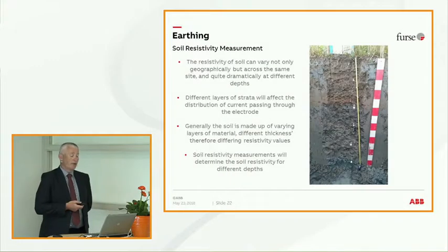When we're measuring the soil resistivity, like I say, we measure it at different depths. This is normally done by a Wenner system. I don't know if anybody's aware of this, where four probes are put in at periodic places, 10 meters apart, 5 meters apart, 2 meters apart. This can provide an accurate definition of the resistance at that level and at the depth required. So if you've got 10 meter spacings, you're effectively measuring 10 meters down.